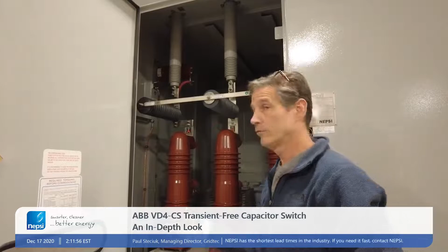You mentioned the sensor must always be on phase A. What about phase rotation? You either have A, B, C rotation or A, C, B rotation. As long as the sensor is on A, whether this is B and C or C and B, it doesn't make a difference because of how the switch operates. This senses a peak, and these two will close when the voltages are equal, whether this is B and that's C or C and B — it doesn't matter. That's why phase rotation does not matter.